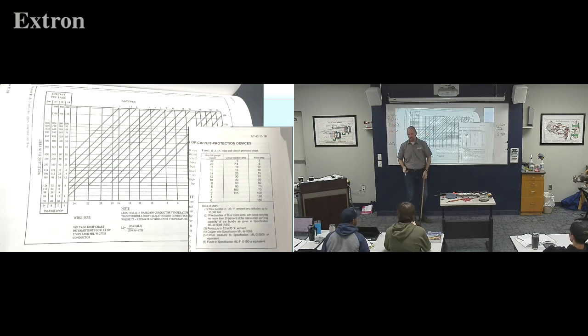The breaker doesn't protect the component, it protects the wire. So, what size breaker do I need to protect my wire now that I know I have a wire size picked out? And I would say, oh, I can't put anything bigger than a 7.5. Let's say I put an 80 amp breaker in. Is that going to protect my wire? No.